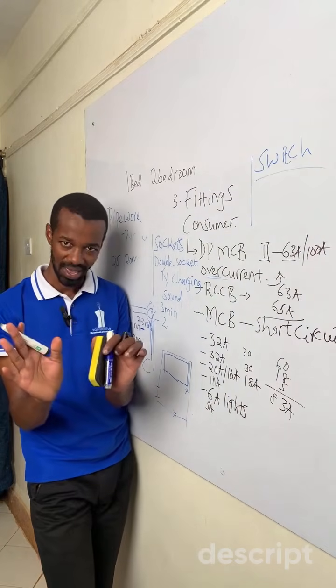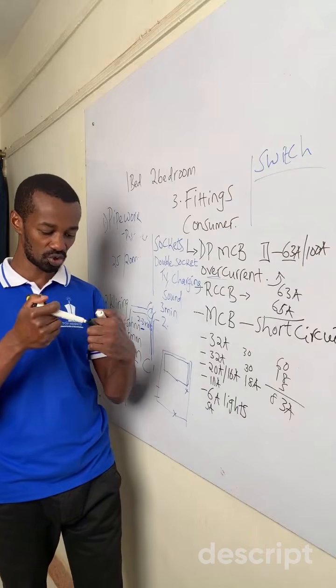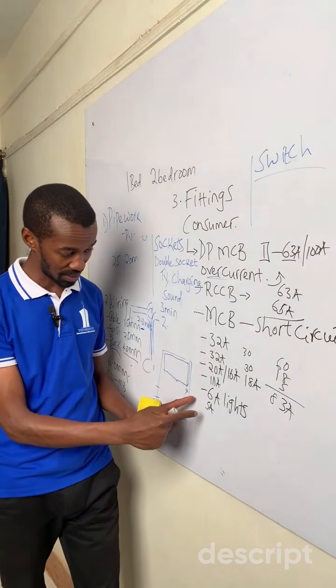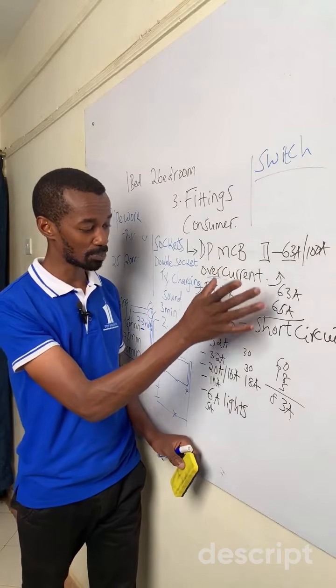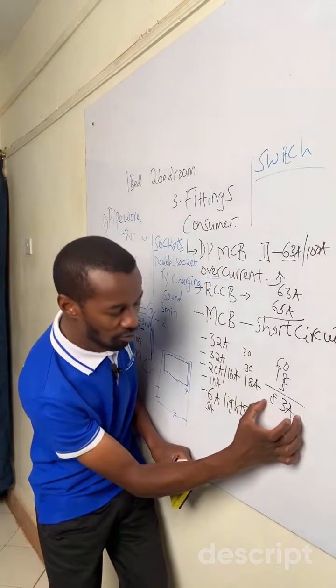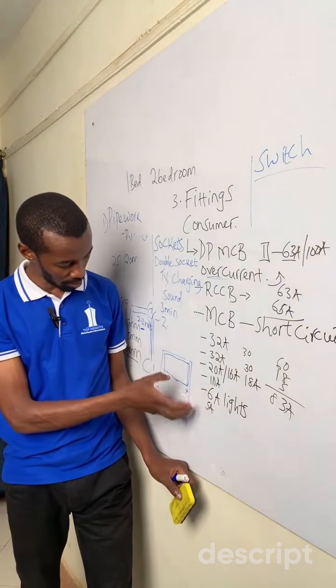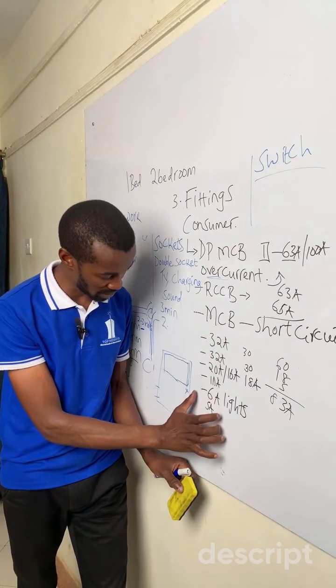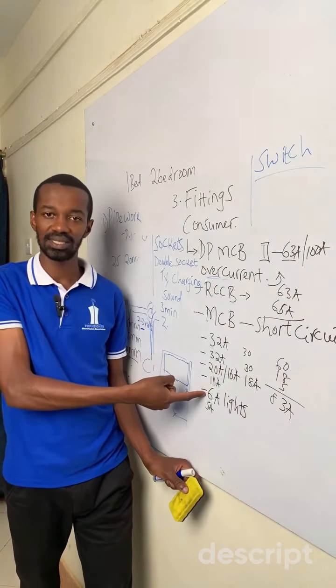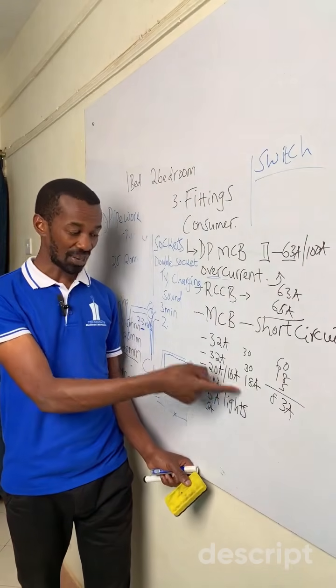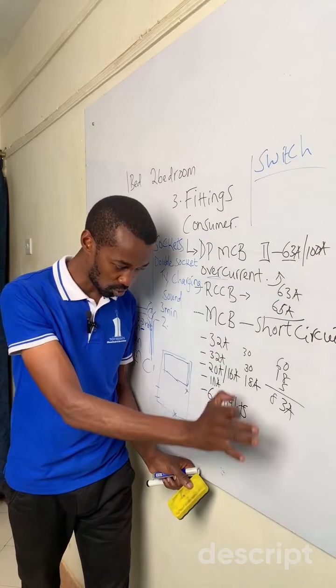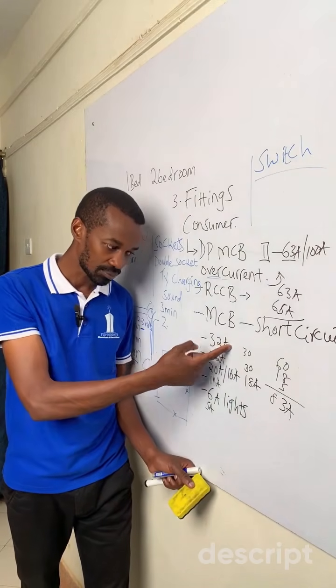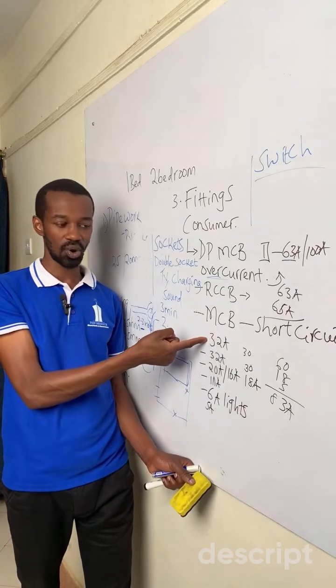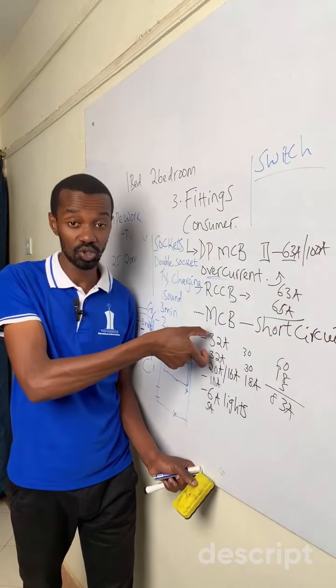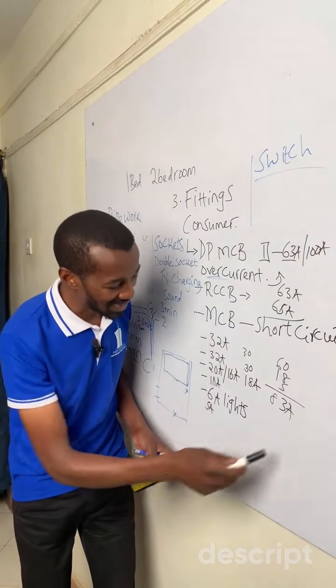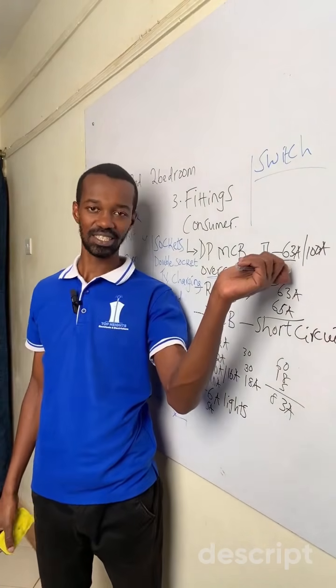That gives 83 amperes. This is how the DP MCB will trip alone, without the individual MCBs, protecting against an overcurrent. This is an overcurrent situation, not an individual circuit fault, because no individual MCB will trip: the lights are not yet at 6 amperes, the sockets are at 18 but not 20 amperes, and the shower and cooker are not yet at 32 amperes each. So there's no cause for alarm for individual circuits to trip, but in totality it is 83 amperes, which exceeds the 63 ampere rating.